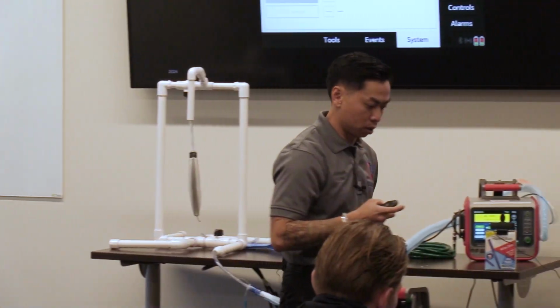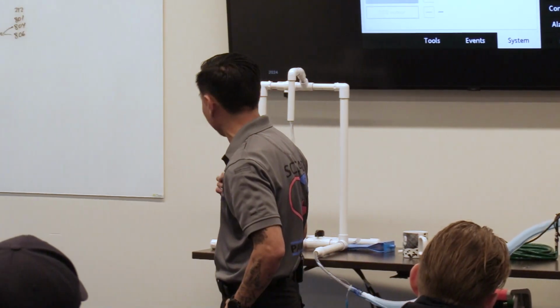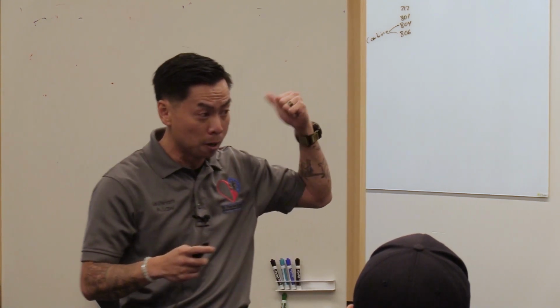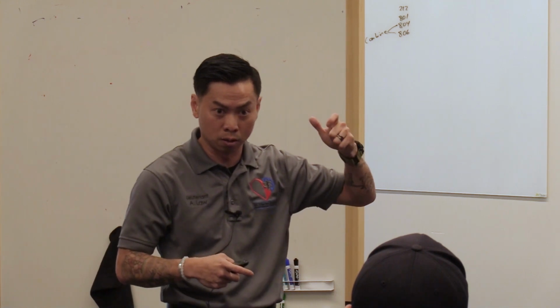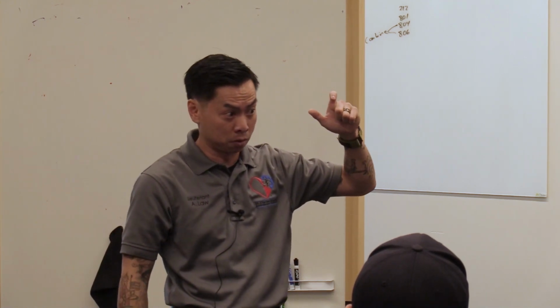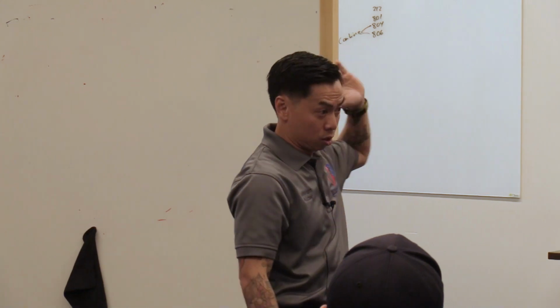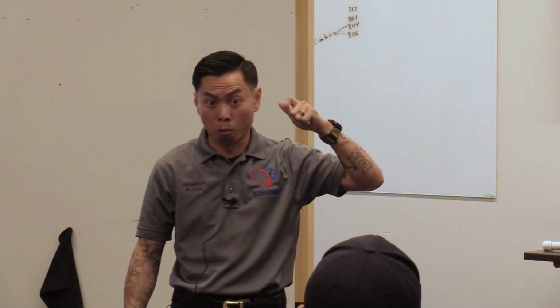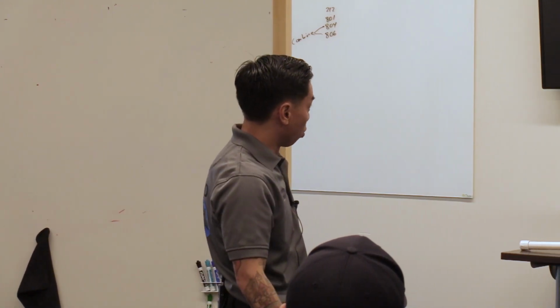The O2 sensor test. I've had mixed stories on this. I've not gotten clear definition or directive on it. Because when we were first introduced to it, it was tested once a month. And then at some point, I guess through the super user, they said that they're just going to do it during BMIS. Either way, the short story is every time you test that, you burn through the O2 sensor cell. And that cell is expensive. So you could do the leak test all day and nothing happens, right? You're not wasting anything. But when you do the O2 test, at some point you'll burn through all the cells and they need to replace that cell. And it's expensive.